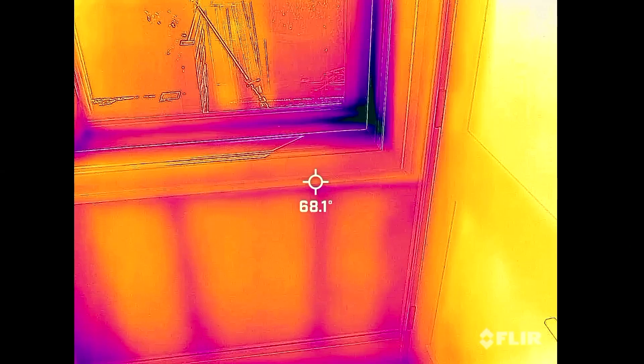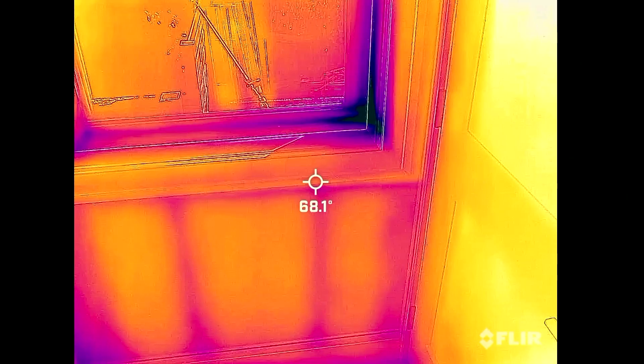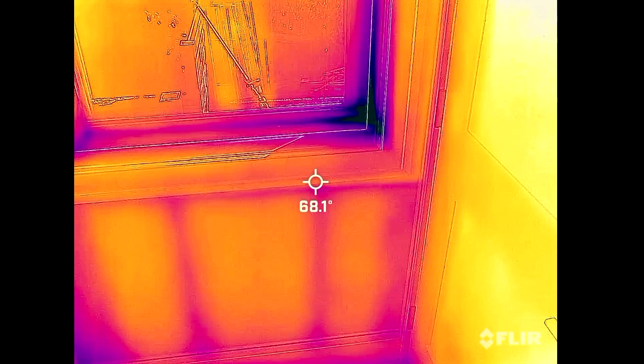Now let's look at that triple-glazed window. You can see the wall temperature around it is pretty high — I have a well-built, very airtight house with two inches of exterior insulation. The wall temperature on this really cold day is 68 degrees. Through the FLIR gun you can actually see my individual studs, and you can tell it's a little colder in the corner since cold shows as dark and warm shows as yellow on this camera.